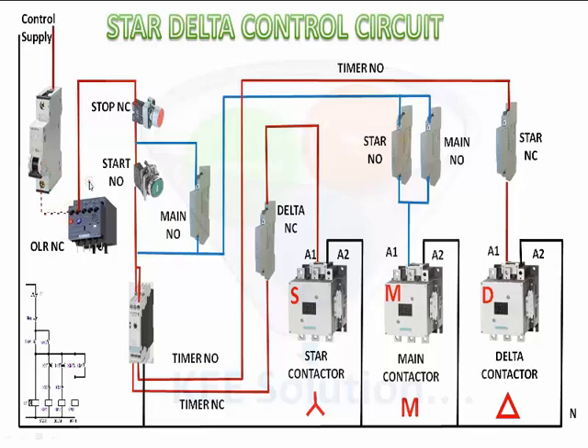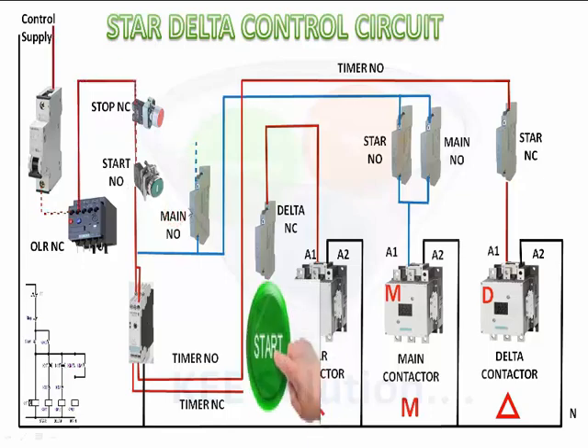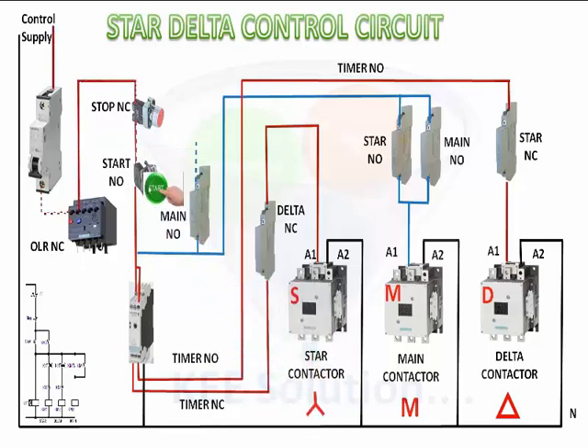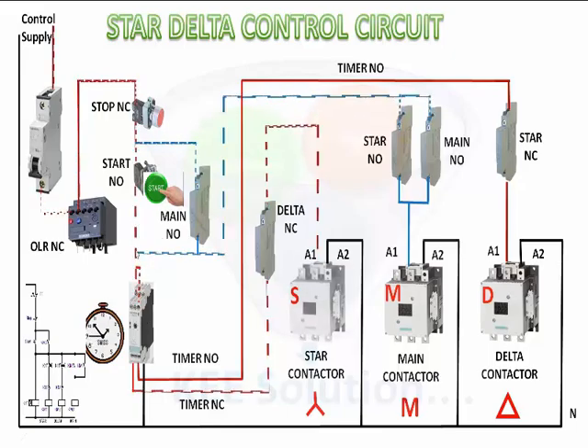Power comes through the MCB, overload relay, and stop NC, and it gets stuck at the start NO or main contactor NO contact. Power will not pass because these contacts are NO. When we press the start button, the timer will start and the control circuit will activate.